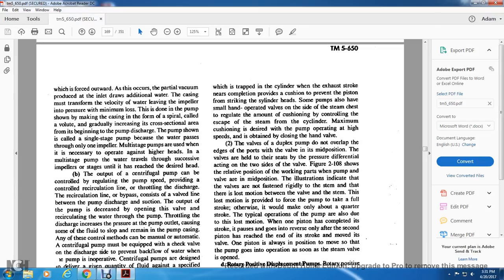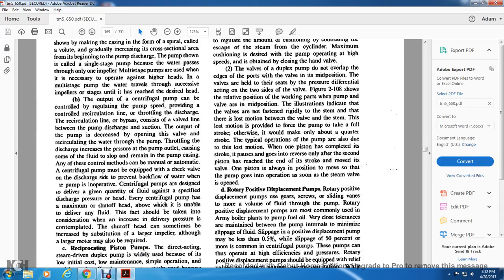This action produces a partial vacuum at the inlet, which draws in additional water. The casing must transfer the velocity of the water leaving the impeller into pressure with minimum loss. This is done in the pump shown by making the casing in the form of a spiral, called the volute, which gradually increases in cross-sectional area from its beginning to the pump discharge. The pump shown is called a single-stage pump, because the water passes through only one impeller. Multiple-stage pumps are also used when it is necessary to operate against higher heads, and in a multiple-stage pump the water travels through successive impeller stages until the desired pressure is reached.